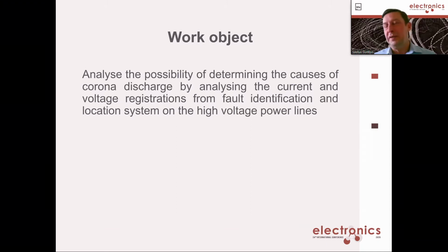Why is it necessary to do this? There are two reasons. One is that corona is a source of losses in the power line, and another is that corona is an indicator that something is wrong in the power line, such as damage to the insulators or other elements.